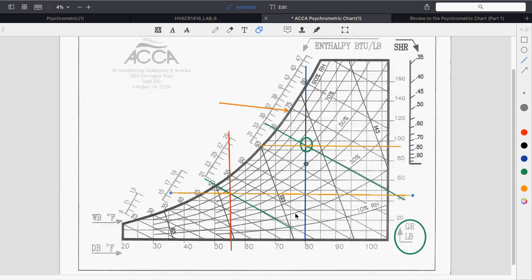Where does that moisture go? It drains off the coil — there's a condensate drain. Part of this whole process includes a calculation telling you how much water comes off per hour of cooling. When designing larger systems and looking at dehumidification, one of the things to account for is the drain size and where this water is going.